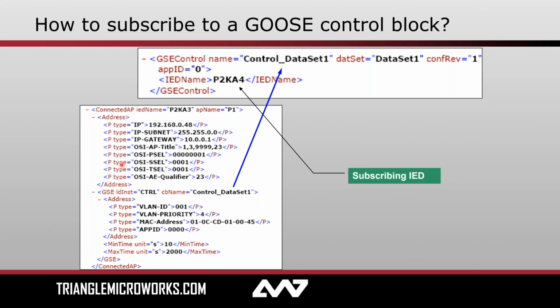So how you actually do the configuration will not be in SCL, system configuration language, what we see up on the screen here. It will be documented in SCL. If you're using a good system configuration tool, this will all be GUI driven, but this is the net result. So we have two different cutouts here from two different parts of an SCD file.